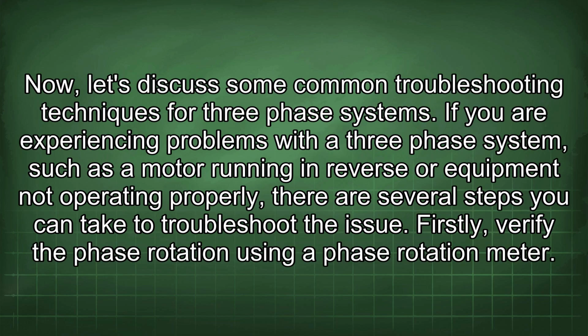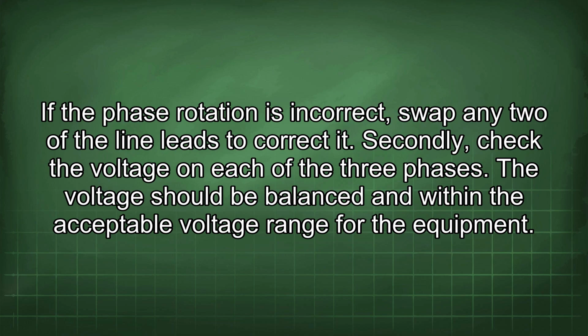Now, let's discuss some common troubleshooting techniques for three-phase systems. If you are experiencing problems with a three-phase system, such as a motor running in reverse or equipment not operating properly, there are several steps you can take to troubleshoot the issue. Firstly, verify the phase rotation using a phase rotation meter. If the phase rotation is incorrect, swap any two of the line leads to correct it. Secondly, check the voltage on each of the three phases. The voltage should be balanced and within the acceptable voltage range for the equipment.